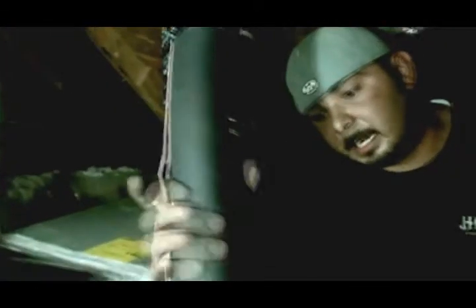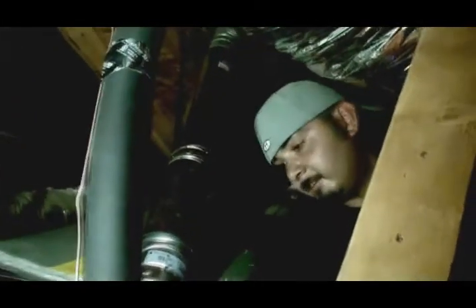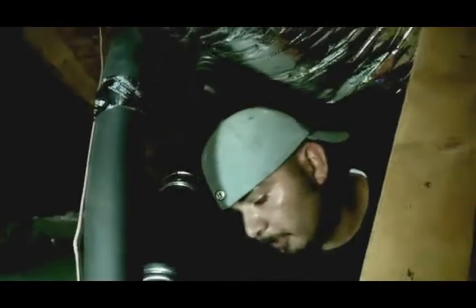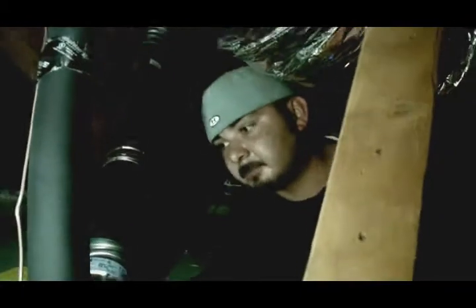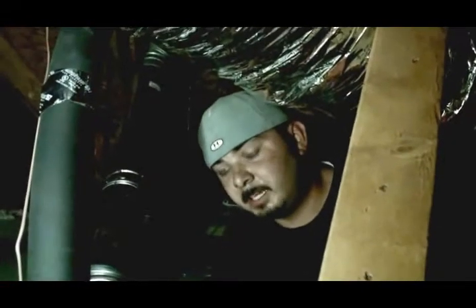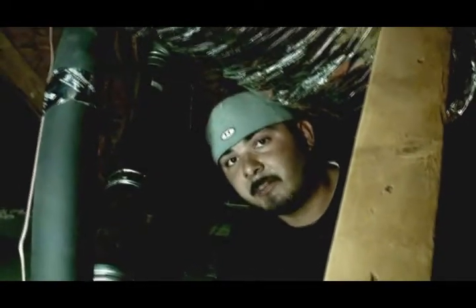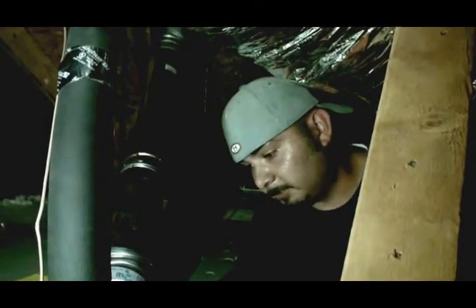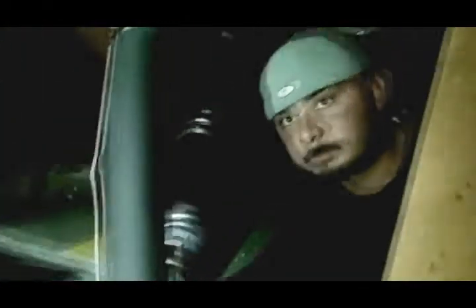We rerouted the copper lines just to make it look a little bit better instead of it laying on the floor. That helps with vibration also sometimes. And pressure tested the lines and made sure everything was good. And we pulled a vacuum for over 45 minutes on that. Just make sure that everything's running properly and stuff like that when we go to charge the system.